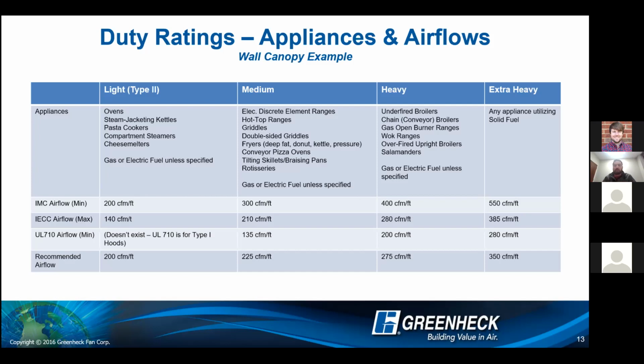So we would recommend an airflow of about 225 CFM per foot for medium, 275 per foot for heavy, and then 350 per foot for extra heavy or solid fuel appliances, keeping in mind that this is a wall canopy hood. So if you were utilizing a wall canopy hood in an island application, as we spoke about earlier, you would want these CFMs to be 20 to 30% higher, depending on the appliance lineup. And again, the guys at Holden are a great reference point for you to determine, in this scenario, what do we think we're going to do CFM wise?